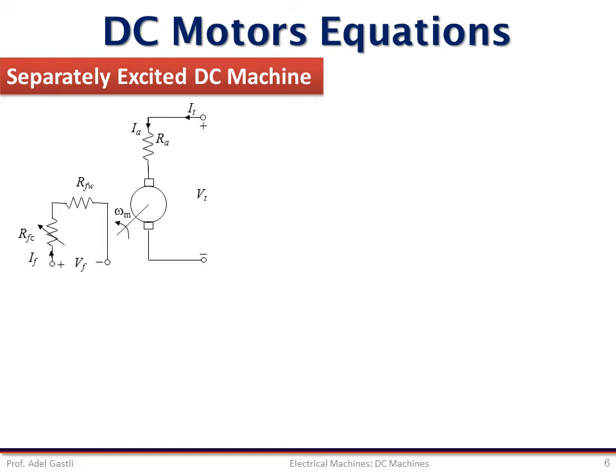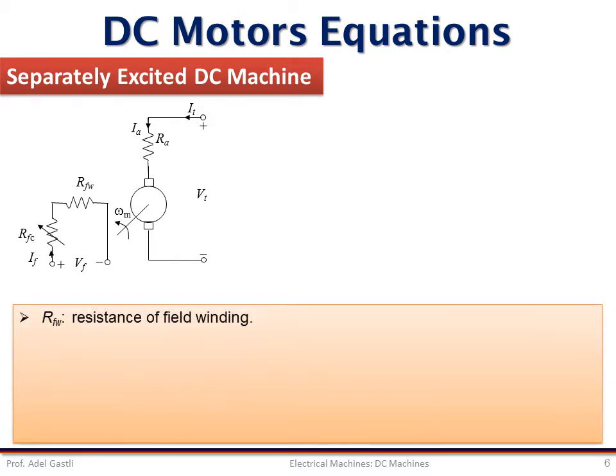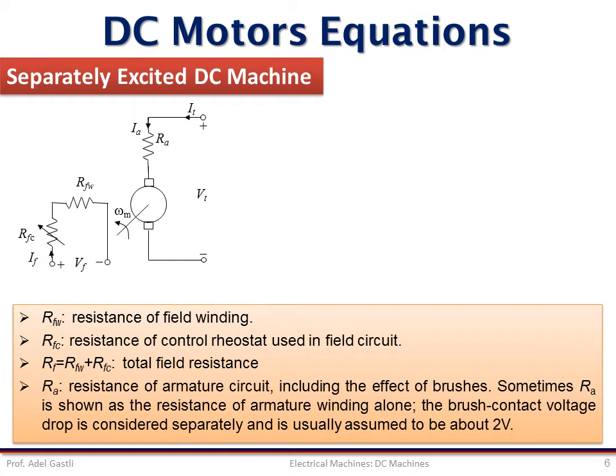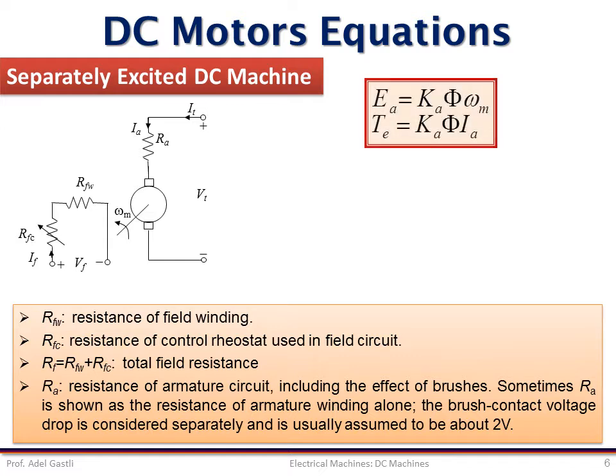A separately excited DC machine can be represented by this equivalent circuit, where RFW is the resistance of the field winding, RFC is the resistance of control rheostat used in the field circuit, and RF is the total field resistance which is the sum of RFW plus RFC. RA is the resistance of the armature circuit including the effect of brushes. Sometimes RA is shown as the resistance of armature winding alone. The brush contact voltage drop is considered separately and is usually assumed to be about 2 volts. Recall that in part 3 we demonstrated the expression of the back EMF and developed torque as a function of flux, speed, and armature current. These equations apply to all types of DC machines and do not depend on any classification.